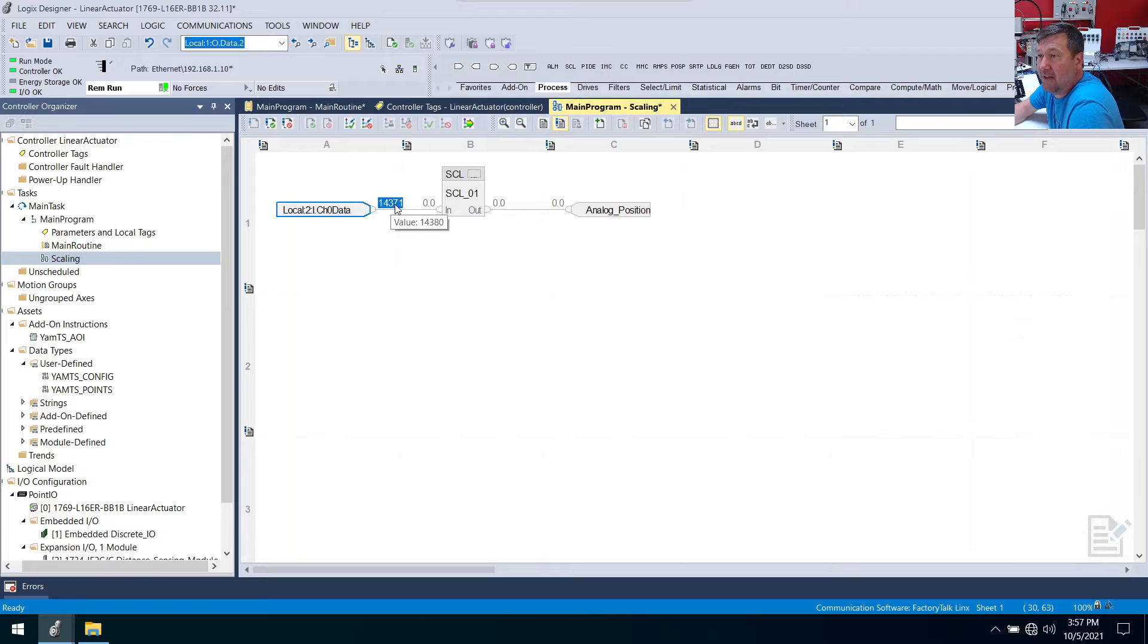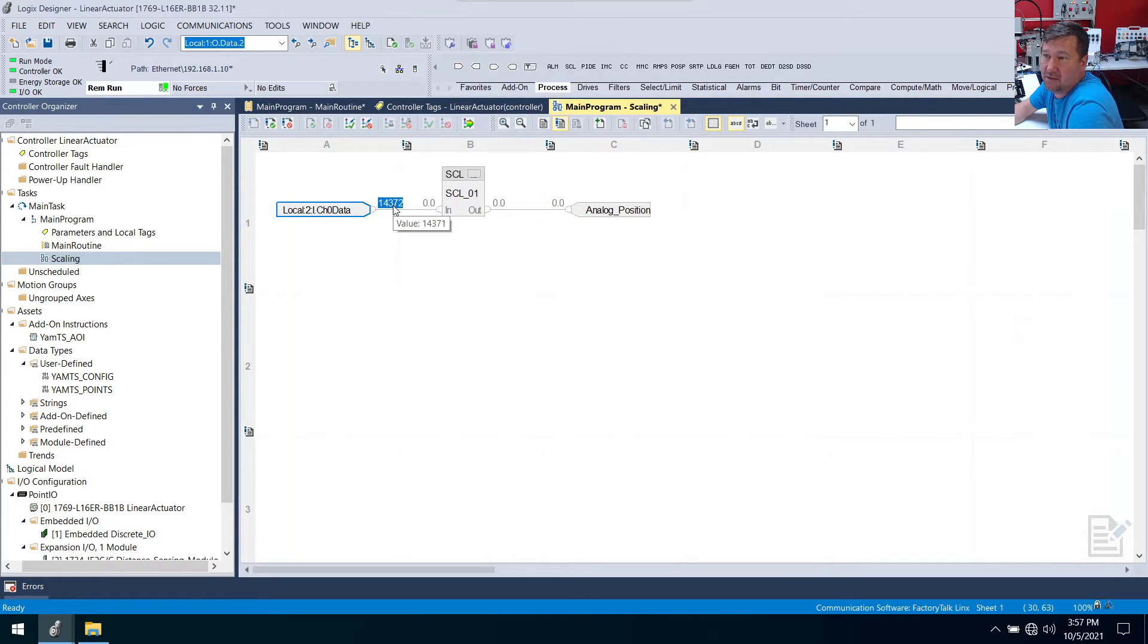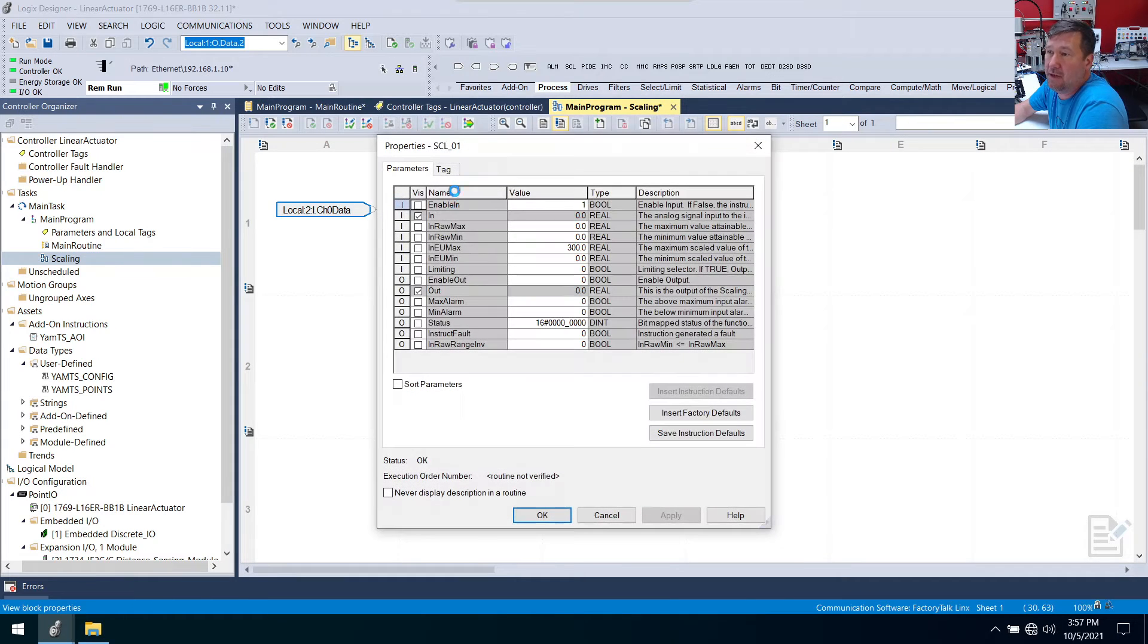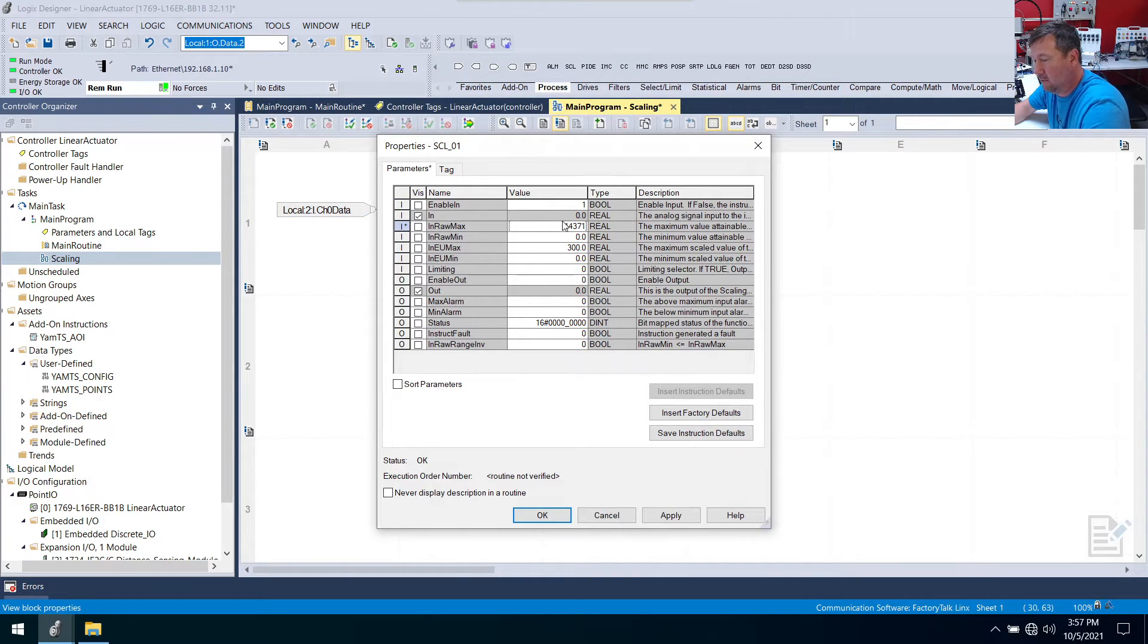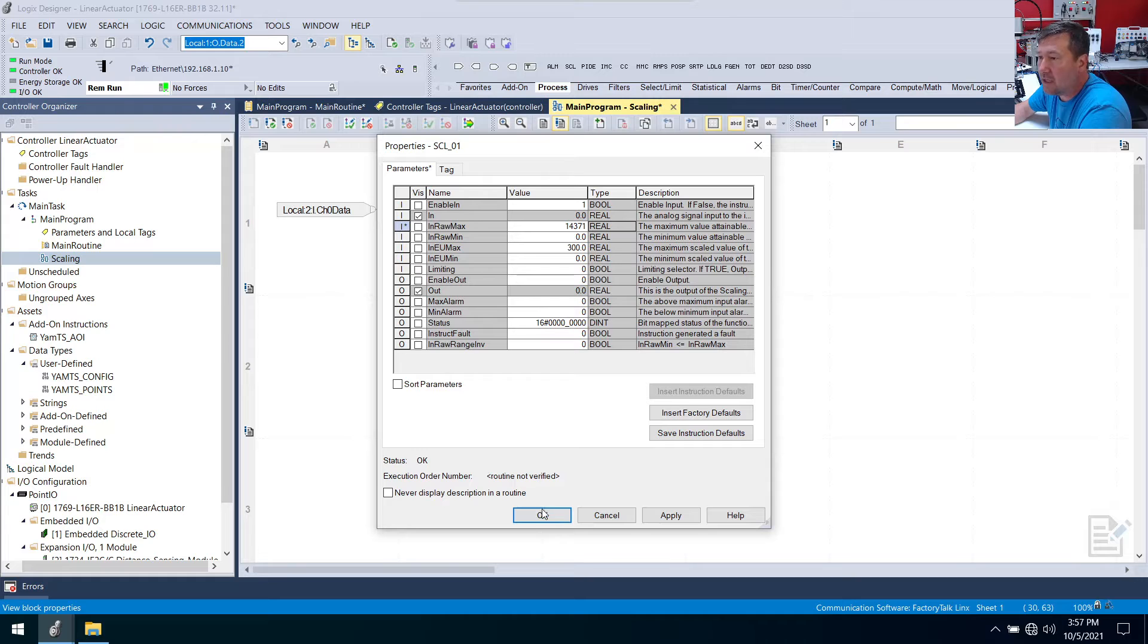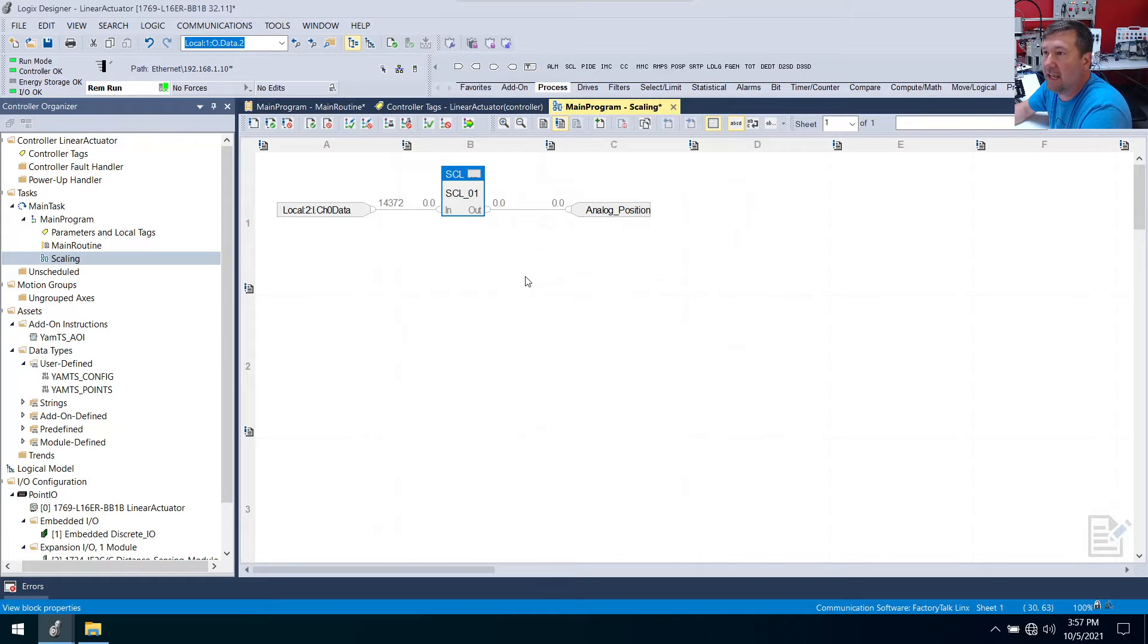And we can see our position is 300.0 millimeters right now. So this value that we're seeing is somewhere right around 14,371. That's our 300 millimeter value. So for our raw max, we're going to put 14,371. Enter, and okay.